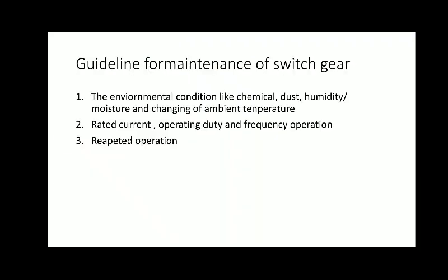After that, there is some guideline for maintenance of switch gear. So what is the guideline for maintenance of switch gear? Inspection, servicing, examination and overhaul depend upon different points. So which points are there? First one, the environmental condition like chemical, dust, humidity, moisture and changing of ambient temperature. Next one, rated current, operating duty and frequency of operation.